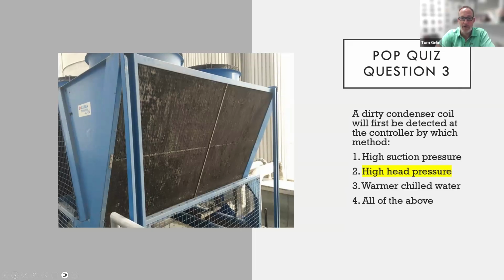So if you have a dirty condenser coil, what's not happening? What's not happening is there's not enough heat transfer, extraction of heat to change the gas into a liquid. So that means that the pressure in the condenser will be higher. That's coming off the compressor. So it means the higher head pressure, the higher discharge pressure.